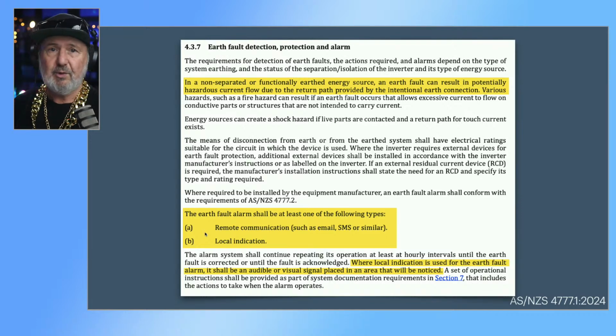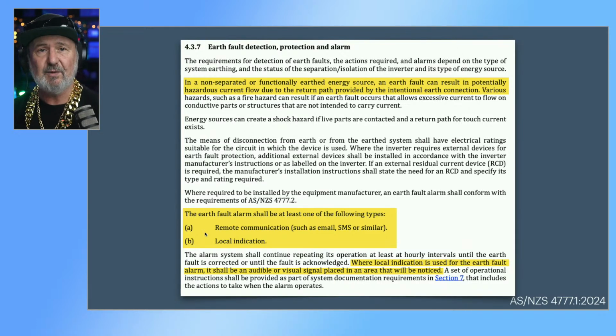Okay. 4777 part 1, I'm just trying to get all the angles on earth fault detection and alarm requirements. So now we're up to date with the latest version of 4777 part 1, the installation standard for inverter systems. And it requires that if in a non-separated or functionally earthed energy source, an earth fault can result in potentially hazardous current flow due to the return path provided by the intentional earth connection. So it's basically pointing out what the problem is. What is a functionally earthed energy source? So for instance, if you connect the positive or the negative of a battery to earth, that's called functional earthing.